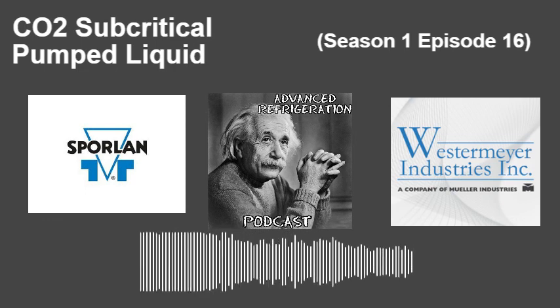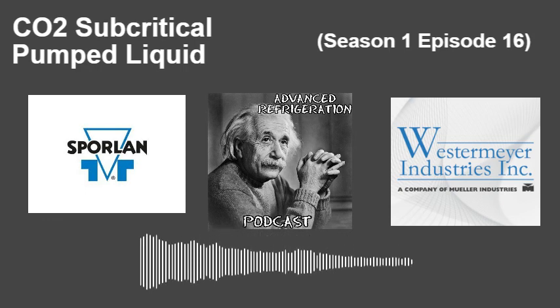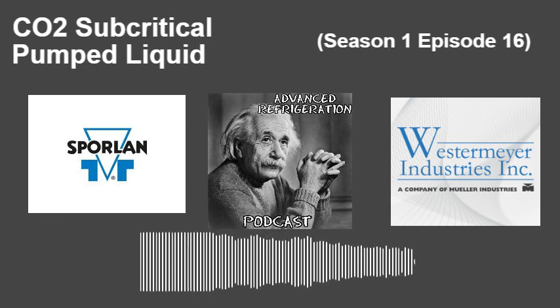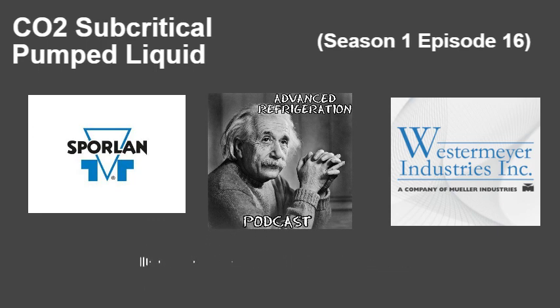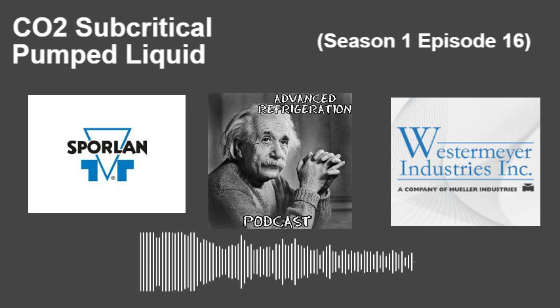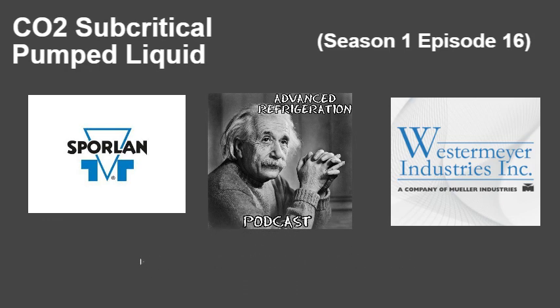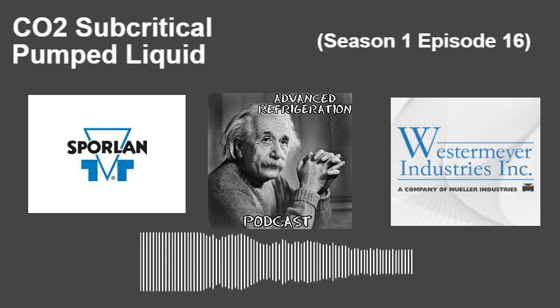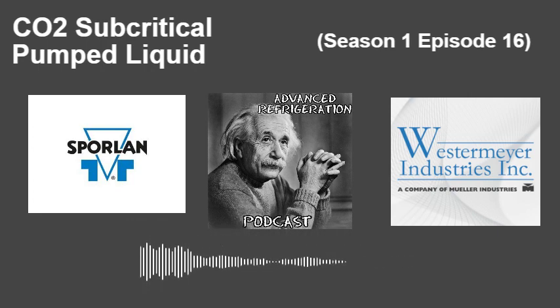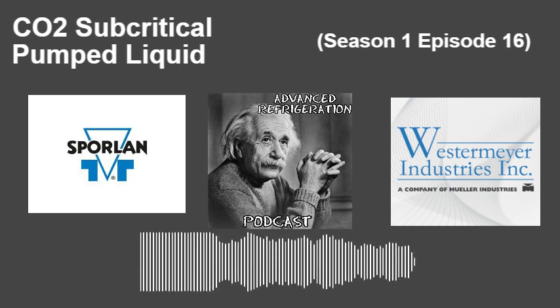I get it. But yeah, you can put it in a case. Just a little advice here: pull the Schrader. Don't put it through a set of gauges, it's going to take forever. So pull the Schrader. But if the Schrader gets stuck in the core puller, walk away. Don't shoot it out like you would normally if it's stuck, because it's coming out a lot faster, and it hurts. I don't know how many I probably shot across the store like that by accident. You think it's got 50 pounds on there, and it's 300 pounds. You're going to have a bad time. Yeah, especially if the bottom piece breaks off in there.